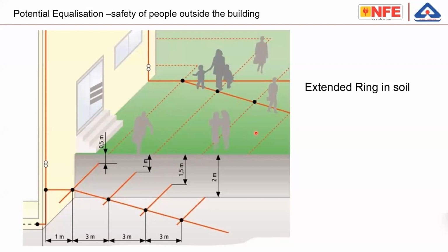This is a kind of voltage grading. So by extending these rings, step voltages can be controlled, and people outside the building are safe in this particular case. Else, you can also make an RCC flooring outside the building, and the RCC flooring and the down conductor can be connected together. As a result, you can make an equipotential bonding also. To protect people outside the building, this is required. Don't think that you have an air terminal, you have a down conductor, and you have one earth electrode, and then the rest is safe. No, it is not like that. You have to keep the distances, or put appropriate measures in place, to protect people who are outside the building.